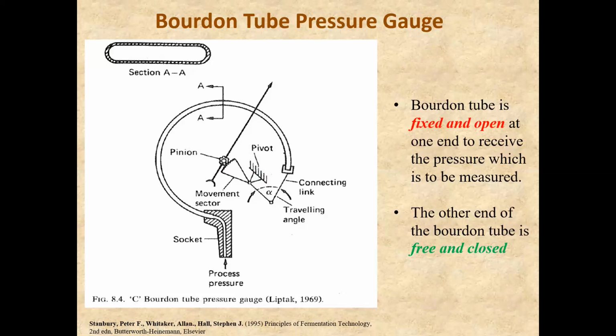And the rotation of the pinion will cause the movement of this pointer as well, as the pinion is connected to the pointer, and the pointer will assume a new position on a pressure calibrated scale. Because this is graduated or calibrated from outside, it will assume a new position, and it will indicate the applied pressure directly, and how much this part will move depends on the pressure of the liquid or gas, whether it's high pressure or low pressure.